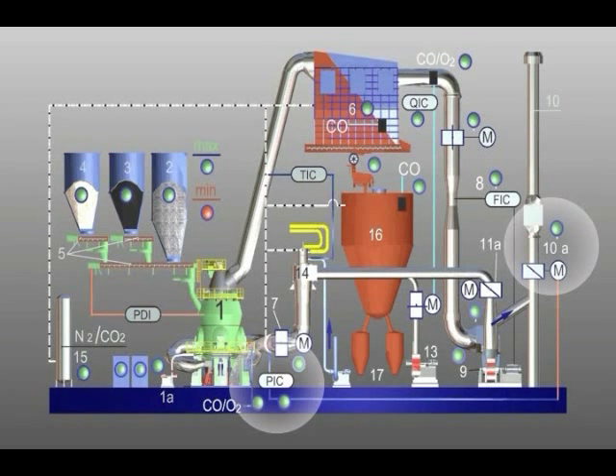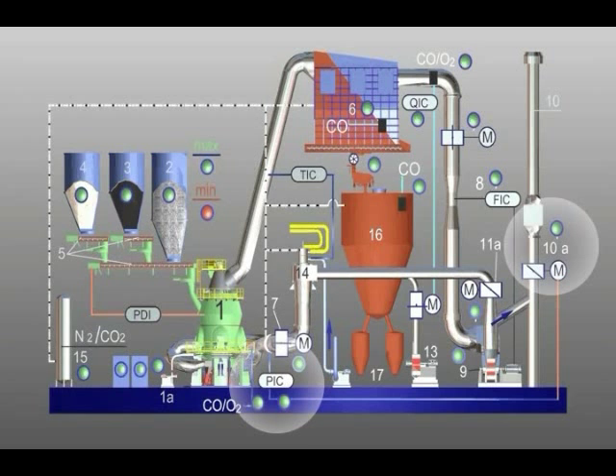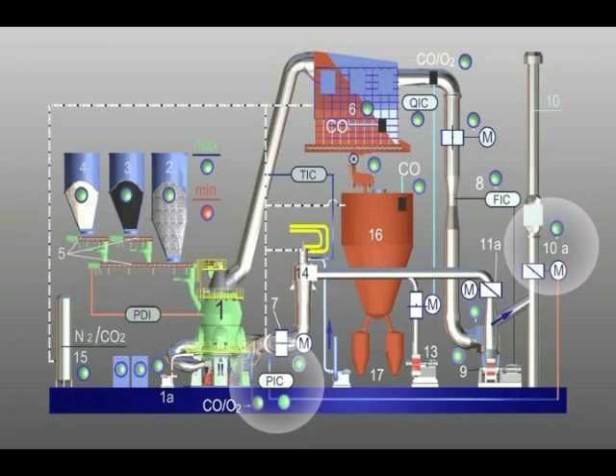The volume flows of process gas within the system are regulated via suction pressure control. The controlled system consists of measuring the suction pressure before the mill and the regulating flap valve for the exhaust gas flow in the stack, position 10A. The set point on the pressure regulator, PIC, before the mill, is usually set to a value of around minus 3 millibar.